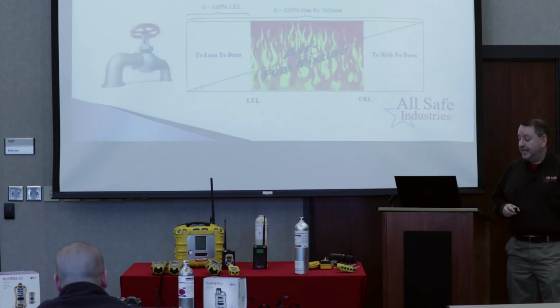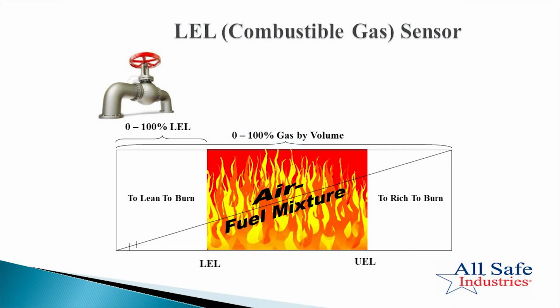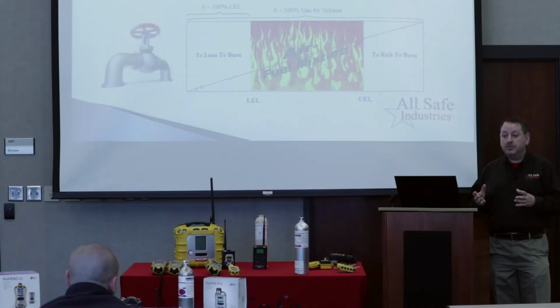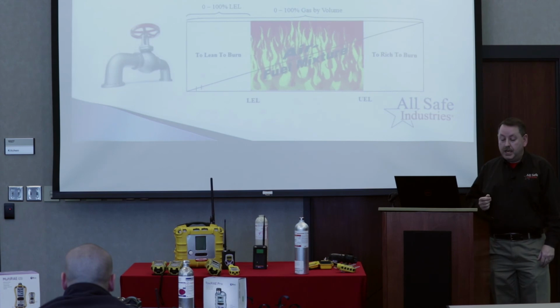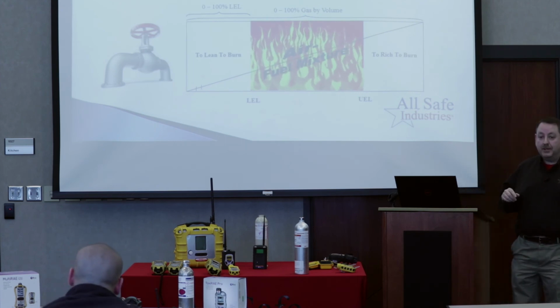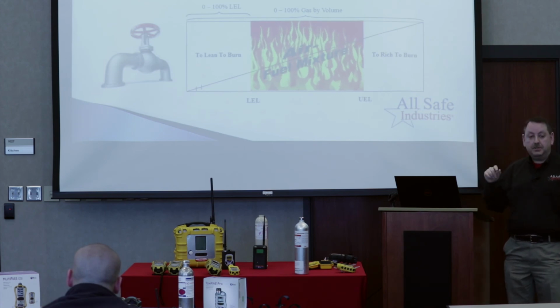So now let's talk about the LEL sensor. And again, the LEL stands for lower explosive limit. It's your lowest concentration of an air-fuel mixture where you have all the right properties for fire or explosion, okay? It's your combustible gas, flammable gas sensor, and it reacts to a wide variety of vapors, okay? So it measures the fuel leg of the fire triangle. So you guys know more about the fire triangle than I do, but I've got it listed here. Of course, one leg of the fire triangle is oxygen.